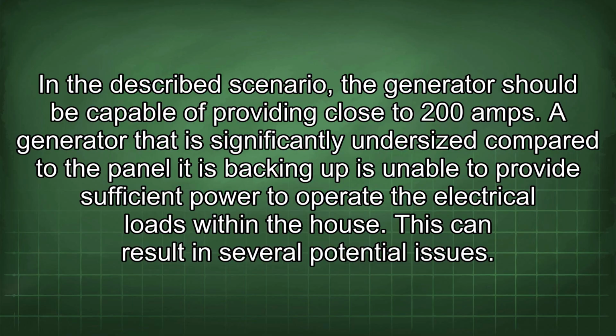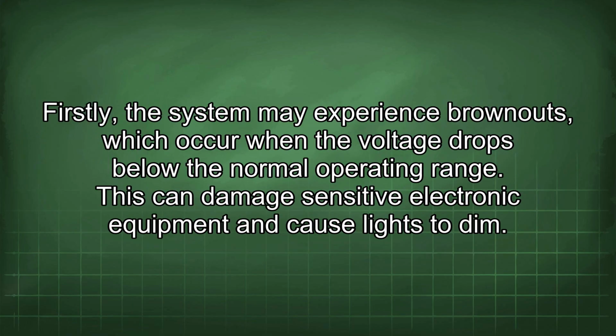A generator that is significantly undersized compared to the panel it is backing up is unable to provide sufficient power to operate the electrical loads within the house. This can result in several potential issues. Firstly, the system may experience brownouts, which occur when the voltage drops below the normal operating range. This can damage sensitive electronic equipment and cause lights to dim.